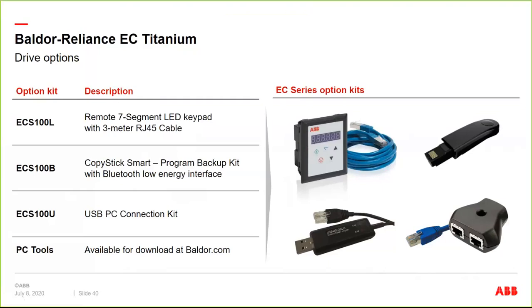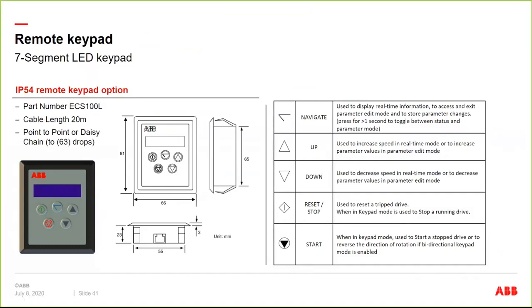From a programming standpoint, if you do a hardwired connection to your PC, that's what this cable is. It's an isolated cable to make sure you get a good connection. Drives put out a lot of noise, so if you don't use an isolated serial to USB cable, chances are you might not make a good communication connection. Again, this is your keypad: start, stop, speed control, and the navigate key gets you into your programming mode. You can daisy chain them up to 63 drops.